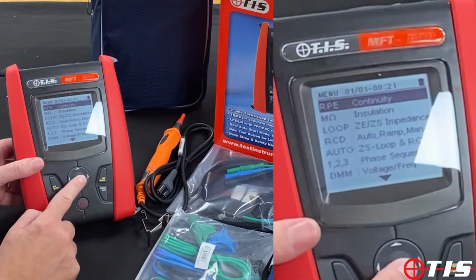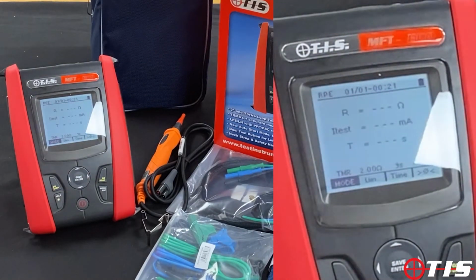Firstly, the unit will do a continuity test. The nice thing about this tester on continuity is you can dial in to carry out continuity tests for up to 99 seconds, so you don't need to keep having to press the button when you're going from circuit to circuit, and the unit will read up to 1999 ohms. So if you're looking at any faults with underfloor heating, it's good for that type of thing as well.